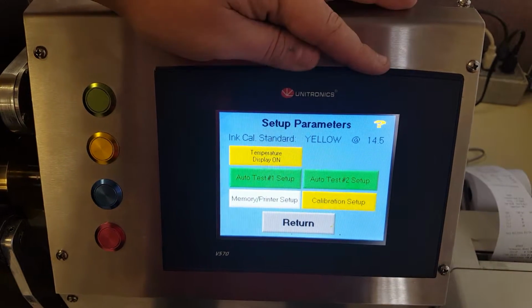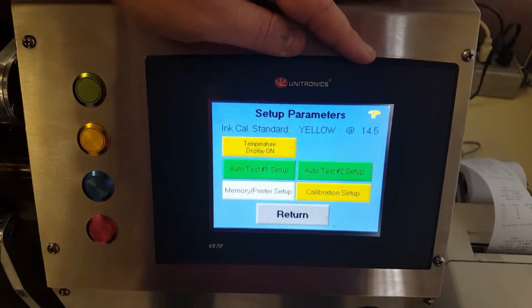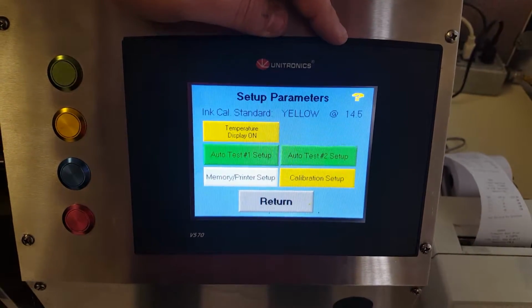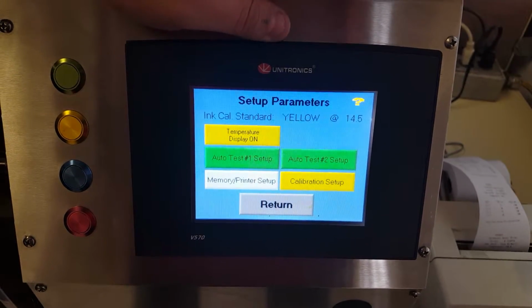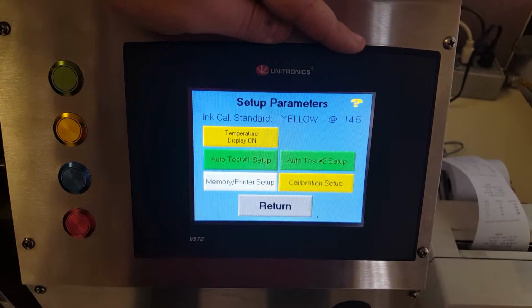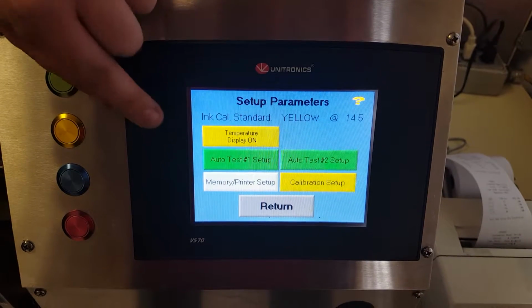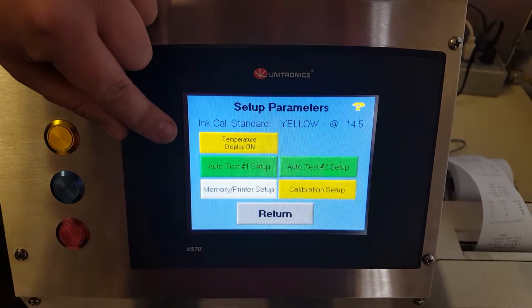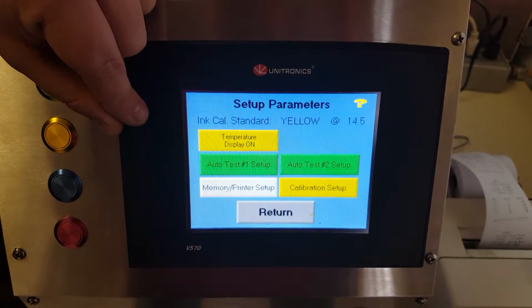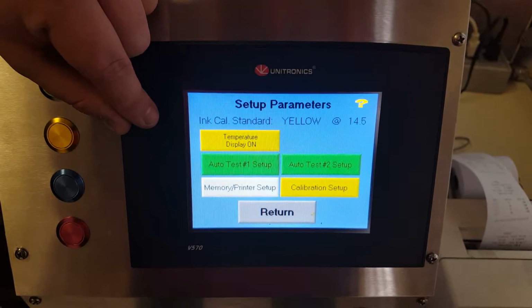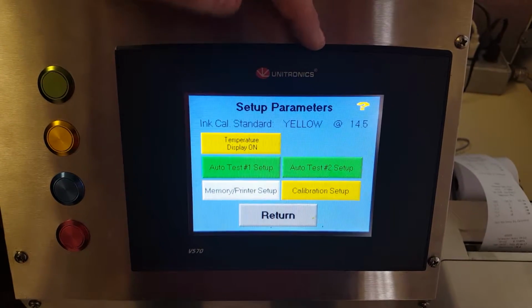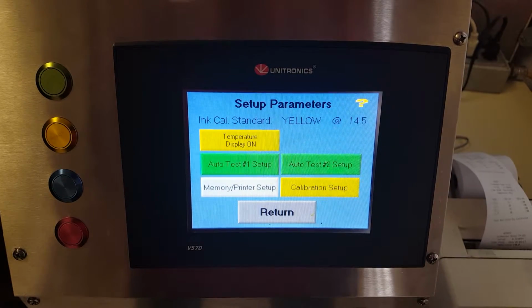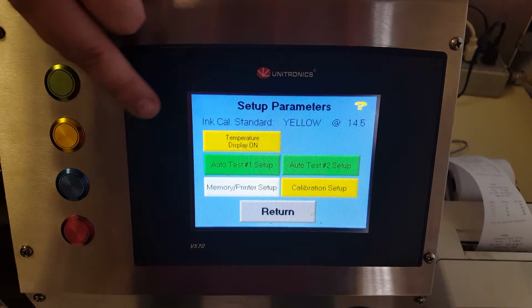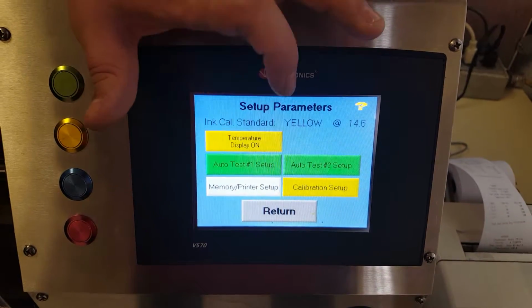Here we have different setup options for each individual parameter of the screen: temperature, speed, test time, and so on. The first thing we see at the top is our temperature display button. This button determines whether you want the temperature displayed here on the PLC, or whether you want to just reference your standalone temperature bath, whichever you choose. You can select that here.